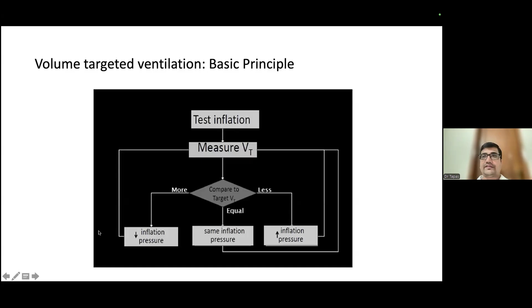However, if the delivered tidal volume equals the set tidal volume, the ventilator will ventilate the lungs with the same inflation pressure. And if the delivered tidal volume is more than the set tidal volume, the ventilator will decrease the working pressure in subsequent breaths, so that the delivered tidal volume matches the set tidal volume.